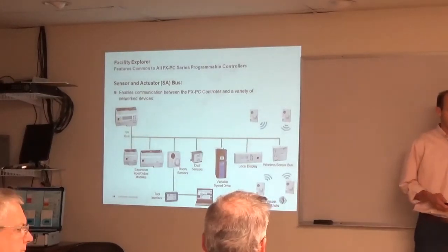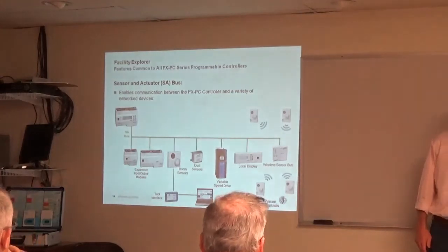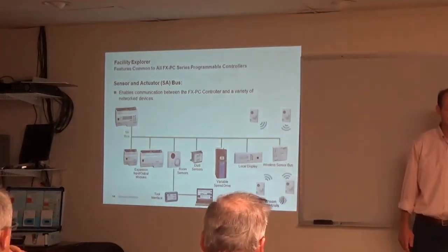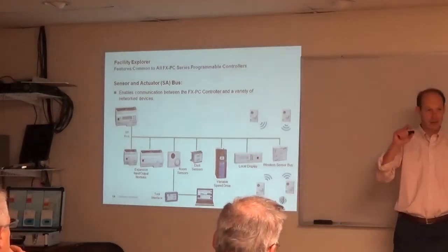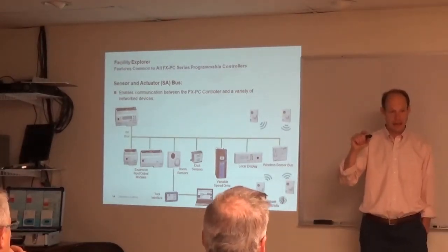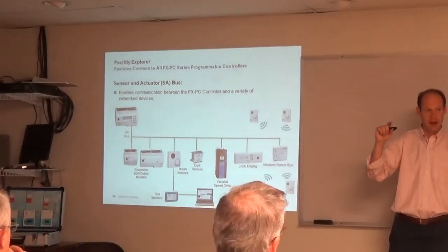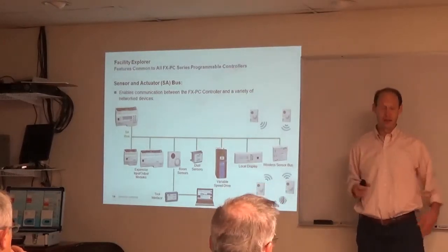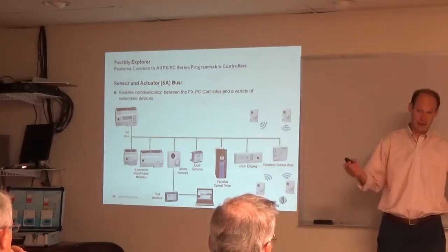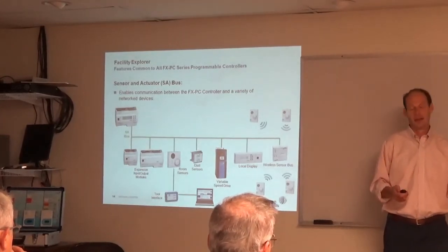On the wireless sensors, what's the average battery life, and is there an indication, any kind of warning that you're running low? Yeah, you can use standard regular batteries, right? Energizer batteries, whatever you want to pick, AA batteries, and they'll last 5 years. If you use the lithium ones, they'll go up to 7 years. So, in one sense, it's good. You don't have to worry about them. Second sense is, yes, I'm going to have to replace batteries at some point in the future.